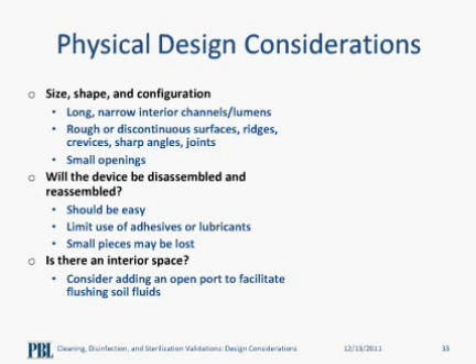The next thing to consider will be the ease of disassembly and reassembly. A multi-component device needs to be disassembled to allow thorough cleaning. We need to take into account the number and size of parts in a device that requires disassembly, and also the potential for incorrect reassembly by the users. It is important to consider the probability of losing parts or breaking the device, resulting in a non-functional device. As a consequence, the personnel performing the cleaning process will become reluctant to disassemble the device, ending up with a device that is not properly cleaned.